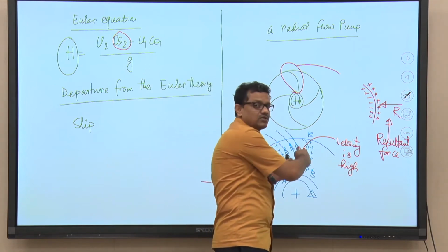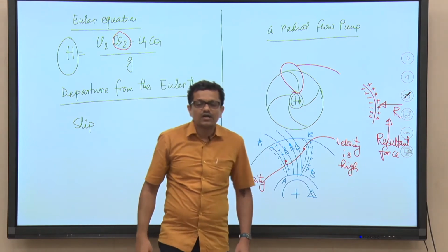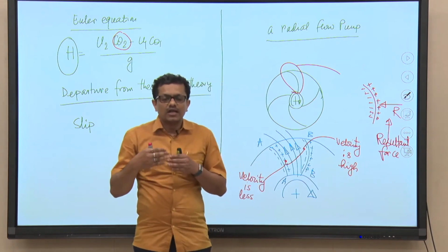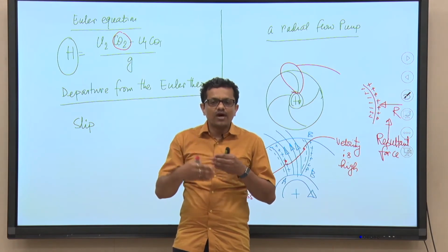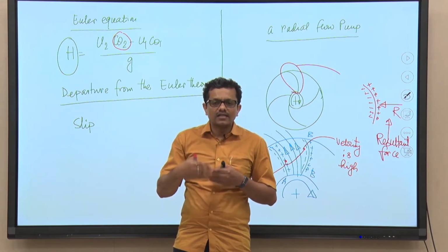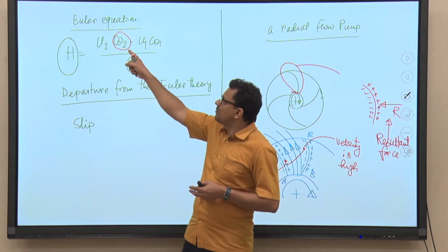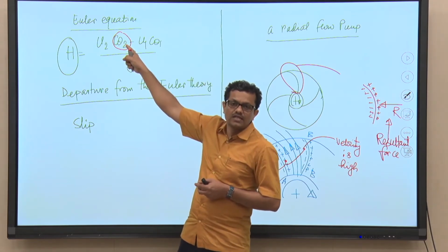for the head that will be developed. But this non-uniform velocity distribution is responsible for the mean velocity leaving the pump impeller at the outlet to be changed from one angle to the other angle, and this phenomenon will eventually result in a diminished whirl component of velocity at the outlet.